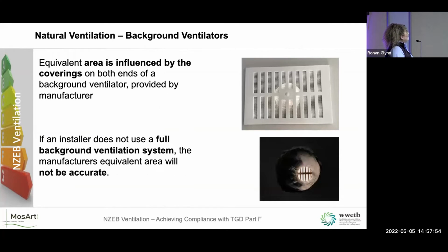The equivalent area is influenced by the coverings on both the ends. So that's provided by the manufacturer. Nobody's expected to work out the free area of that mesh. But what happens a lot of the time, especially BER assessors who tell me, they come along and they find that the outside grill doesn't match the manufacturer of the inside one, and they won't sign off on that. So they have to be by the same manufacturer. If an installer doesn't use the full background ventilation system, the manufacturer's equivalent area will not be accurate. And that's why it doesn't pass the test.